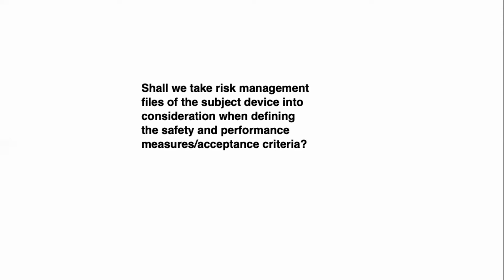So if there's any new information discovered during clinical literature screening, it is looped back to the risk management department of our clients so that they can assess and possibly update their risk management profile of the device prior to the completion of the CER, so that we can put that new information into the CER.